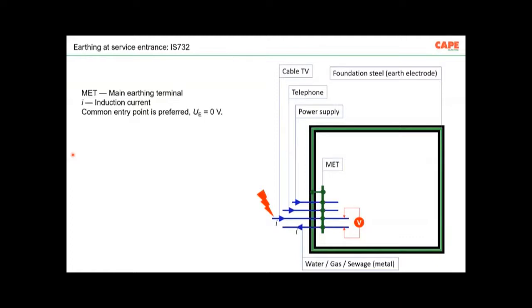The first purpose is protective equipotential bonding. During a fault, people inside the building shall not get a shock. Also, electrically, there shall not be any spark. So the first is no shock, no spark. Number two, in case of a lightning strike on the building or on the service line, the potential differences, the voltage between two service incomings, are reduced to a very low level.